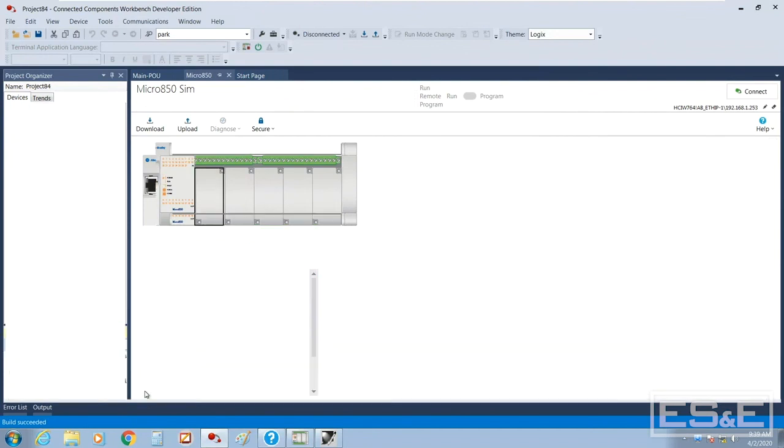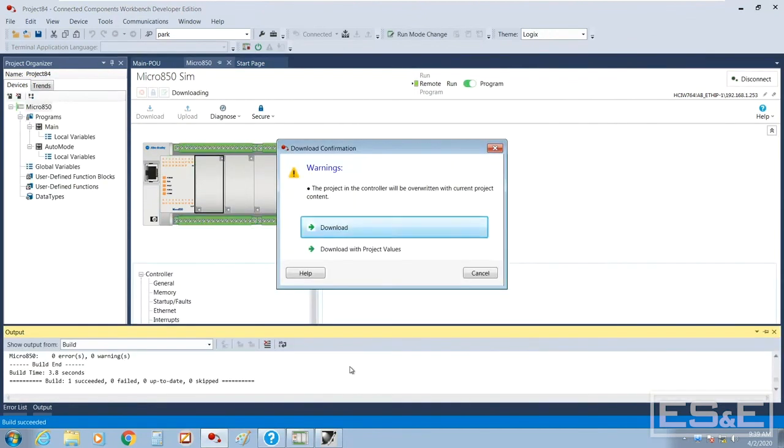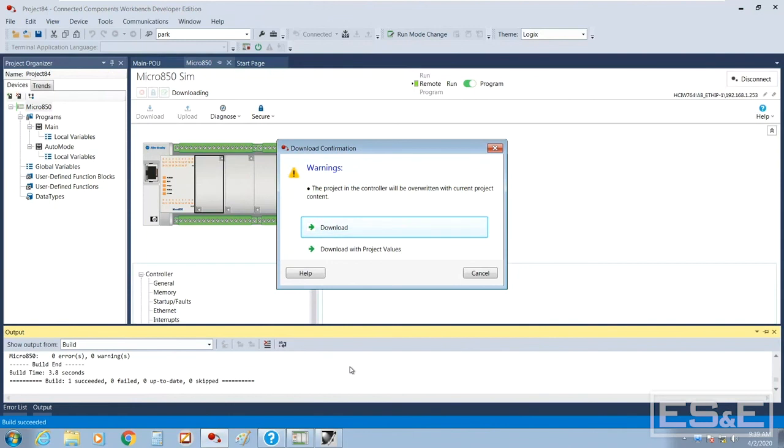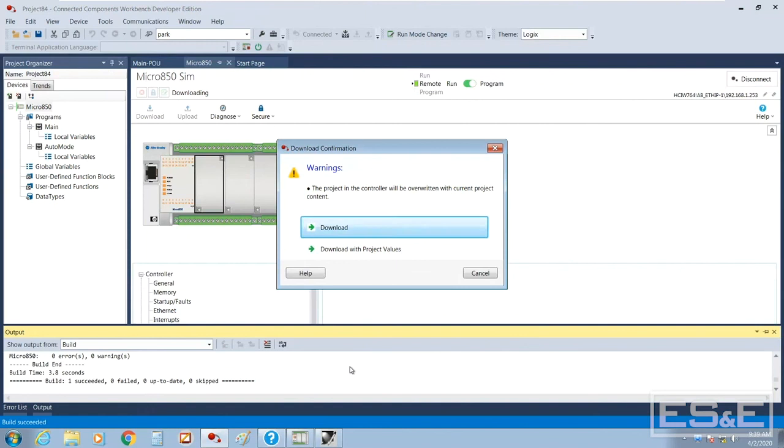So just look down here, you'll see some flashing. So one of the coolest things about CCW is it has this ability that is actually kind of complicated and difficult to do in any of our other editors with any of our other processors. When you do a download it actually prompts you: do you want to download the code and not download the project values? What that would do, if you had values inside the controllers variable tag values, you could download just the code and those values would not be overwritten, and so in that situation you would select download.